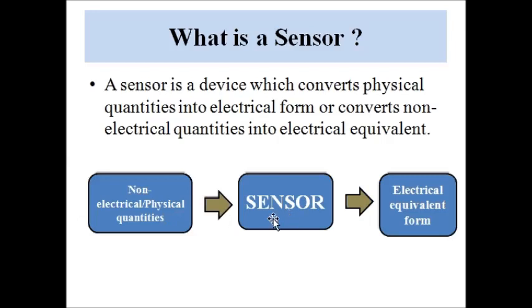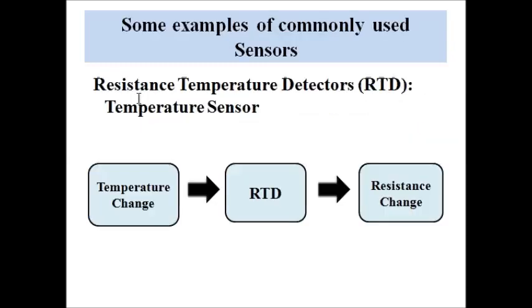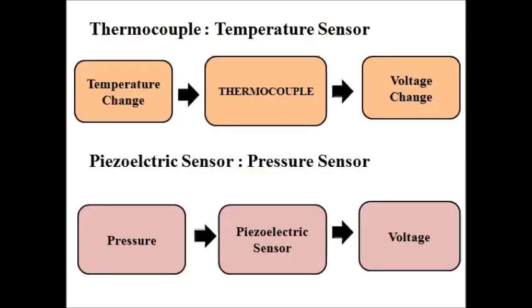Generally, a sensor converts physical quantities into electrical form, normally in the form of voltage or current signals within a standard range. Now let's know about some basic sensors used in day-to-day life, in industries, and other areas for general measurement purposes. The first is the Resistance Temperature Detector, or RTD. It is a temperature sensor — it converts temperature change into resistance change. The RTD converts surrounding, environmental, or any other temperature into a suitable change in resistance, which is then converted into a voltage or current signal by a signal conditioning circuit.